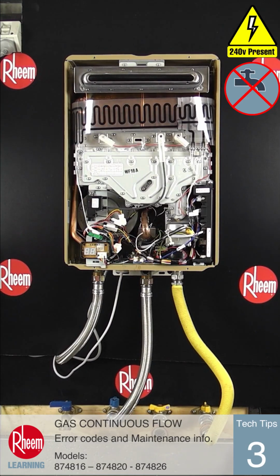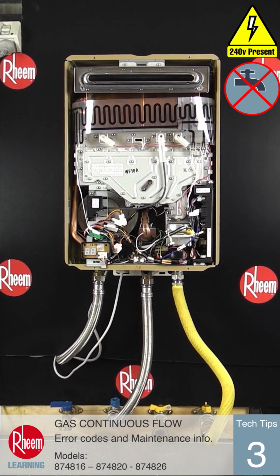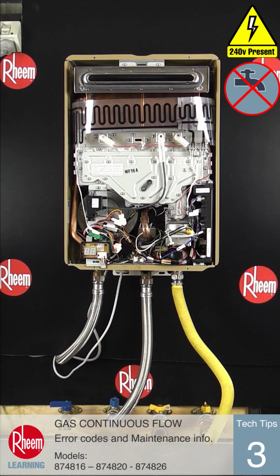The error code history can be cleared when accessing the maintenance data directly from the water heater PCB only. This may be useful for intermittent faults, as the history can be cleared, and if the fault returns over time, the history can be checked again to see if there are fresh, new errors stored.